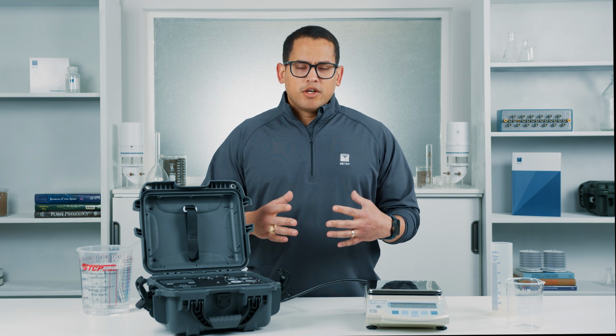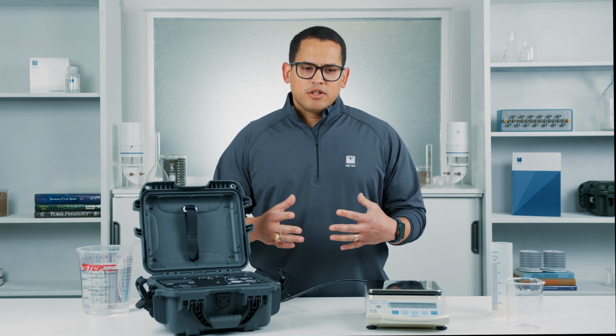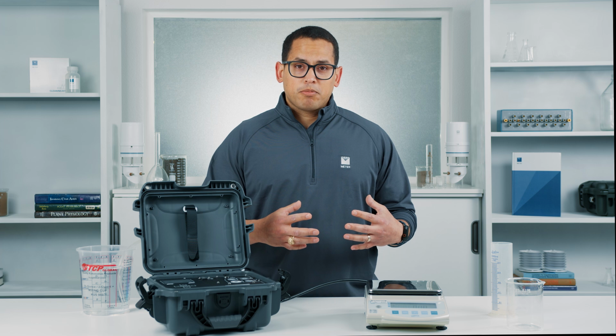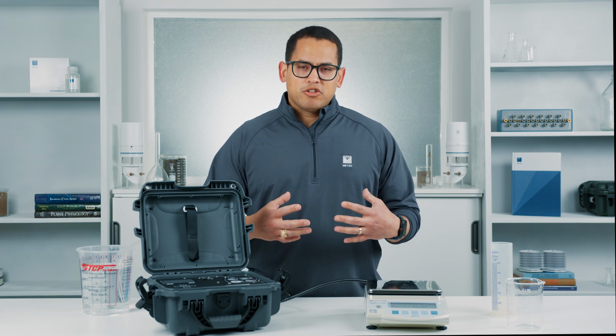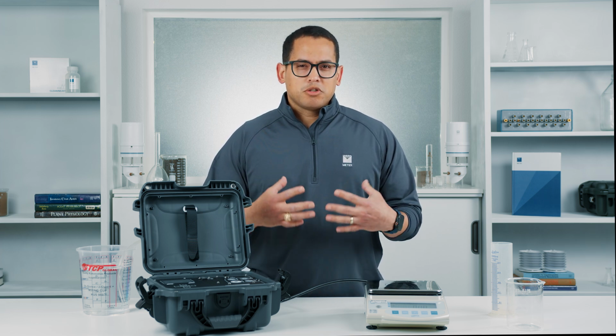Today we're going to go through the water pump calibration process for the SATURO. There are two methods that you can use for calibrating the SATURO. The first is a volume-based method where you will measure out a specific volume from the pump. The other is a mass-based method, which is the more accurate approach and the one that I typically recommend, where you measure a specific mass of water that's being pumped out of the device. And we're going to go through that process today.